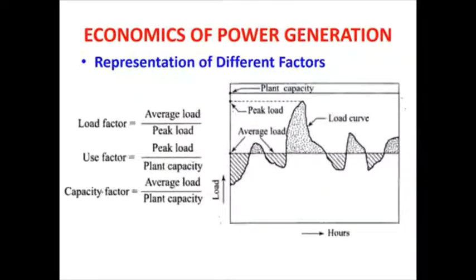Now see, this is a chart which is representing the different factors. So we have written the ratio also. Load factor equals average load by peak load, use factor equals peak load by plant capacity, and capacity factor equals average load divided by plant capacity. So use factor is related with peak load and capacity factor is related with the average load.